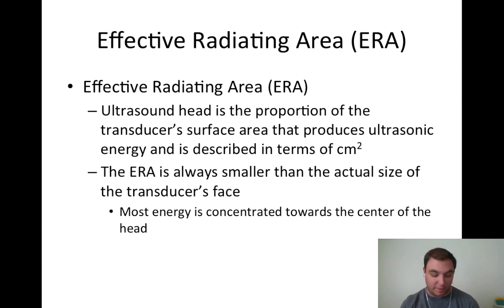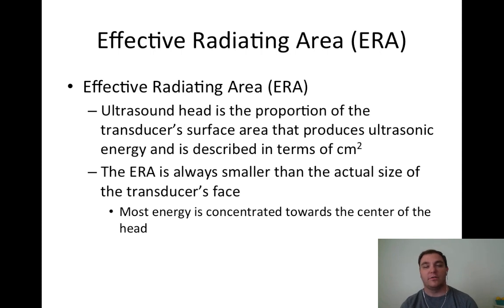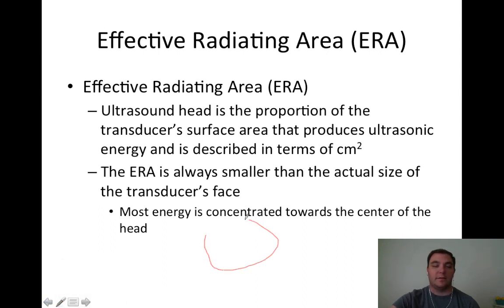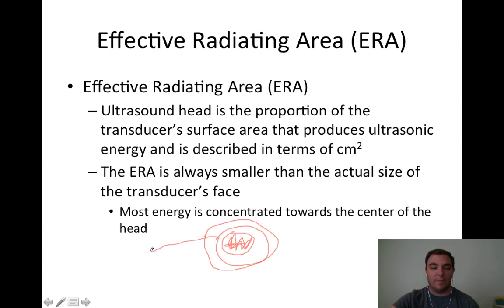The ERA - effective radiating area - is the proportion of the transducer surface area that produces the ultrasonic energy, described in centimeters squared. It is always smaller than the actual size of the transducer face. Most energy is concentrated towards the center of the ultrasound head. The ERA might only be a portion of the face, and the majority of energy is concentrated dead center.